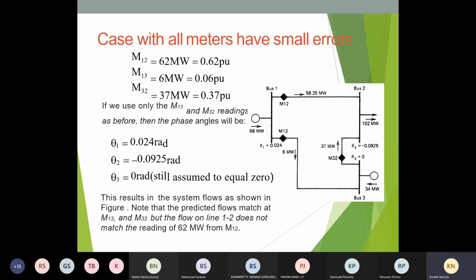Next, we will see the second case, with all the meters having some small errors. Suppose the first meter reads 62 megawatt, in per unit 0.62, M13 reads 6 megawatt and M32 reads 0.37. Using only the M13 and M32 readings, as per the previous calculations, considering the same swing bus theta 3 equal to 0, we get theta 1 as 0.024 radian and theta 2 as minus 0.0925 radian. So what does this result in the system? The predicted flows match M13 and M32, but the flow on line 1-2 does not match the reading of 62. So this way, if any change occurs in any part of the power system, there may be an error in the power system.